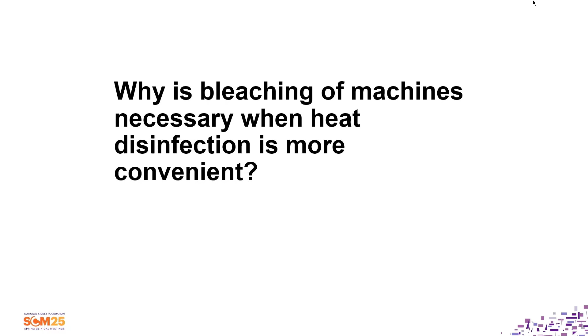Anyway, so it's a cleaning process, and what it cleans is this. In every machine, there is a prism that actually denotes infrared light. When dialysate passes through that, an infrared is transmitted on one side, and on the other side is a receiver. That receiver has to receive the same intensity of light that is being transmitted through that prism. If it doesn't, something is blocking it. And what is usually that thing? Blood. So if that's cloudy because you haven't bleached and denatured it with some of the things that can make it cloudy, is it doing the same thing? Yeah. So if you're getting a lot of false blood leak alarms, somebody's not bleaching your machine.